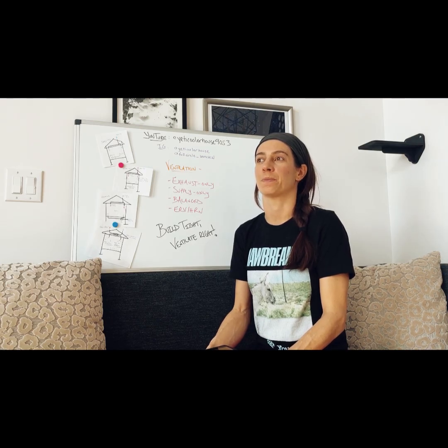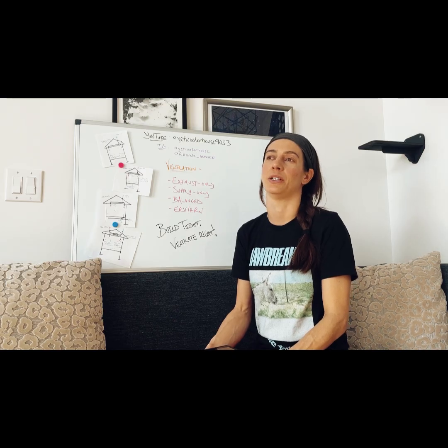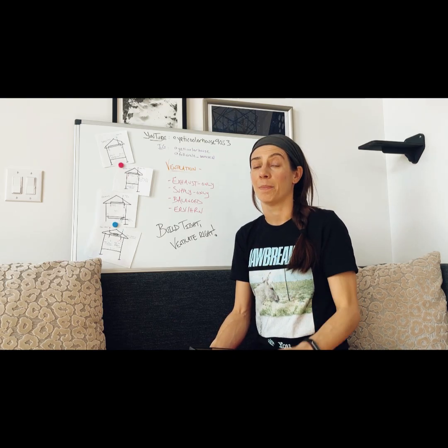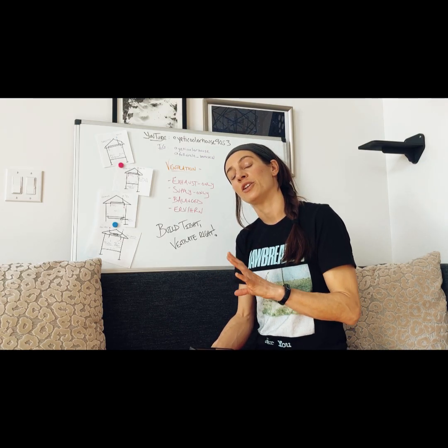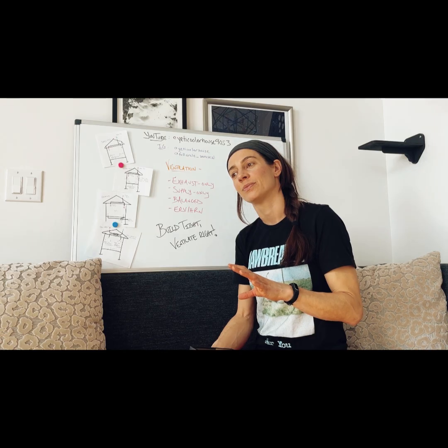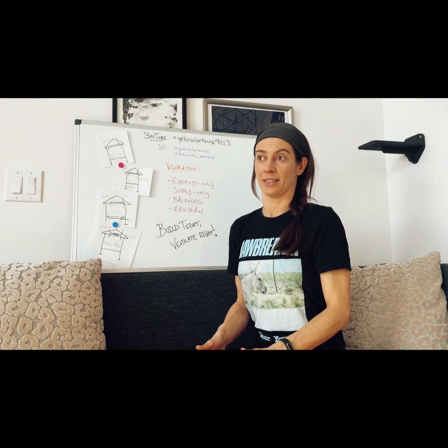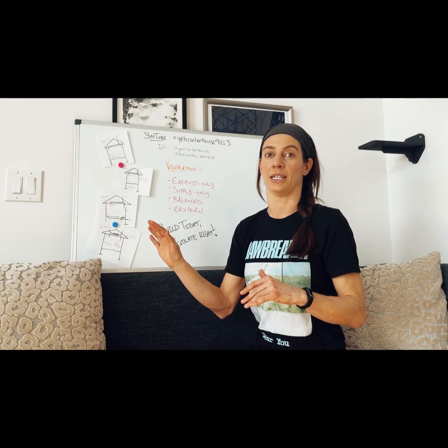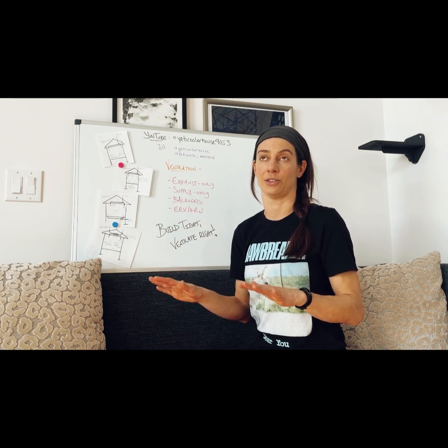So if you are tying it into the existing system, be wary that it might not be totally balanced. But if you install the ERV or HRV totally on its own, that's the way to go, because it doesn't depend on what's happening with the distribution of the heating and cooling. It's just supplying the fresh air and exhausting stale air. It's doing its job.